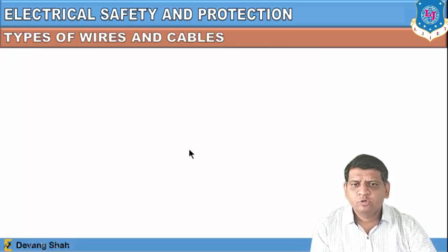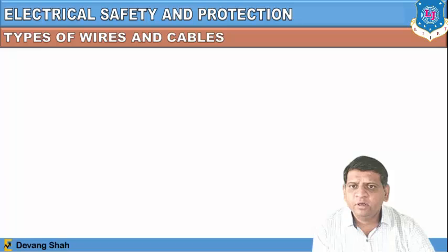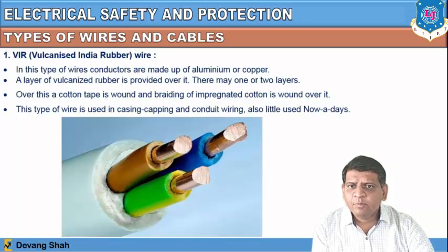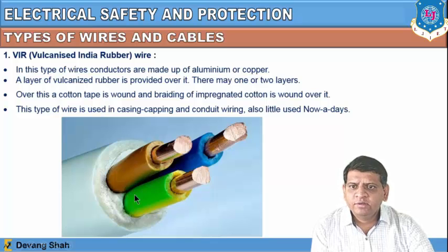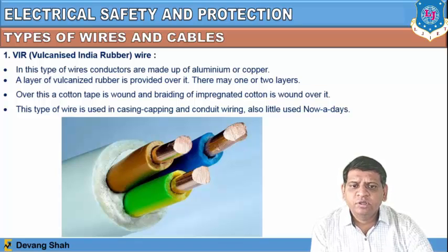Now let us discuss types of wires. The first type is the vulcanized Indian rubber (VIR) wire, where conductors are made of aluminum or copper, a layer of vulcanized rubber is provided, and there may be one or two layers over which a cotton tape and braiding of impregnated cotton is wound. This type is used in casing, capping, and conduit wiring, but is little used nowadays.